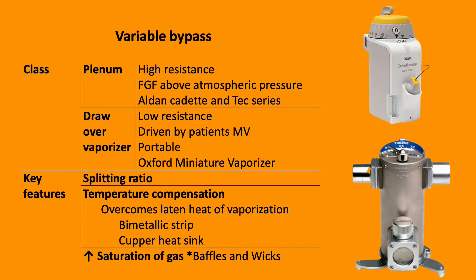Draw-over vaporizers are low resistance, driven by the patient's minute ventilation — they are portable. An example is the Oxford Miniature Vaporizer, shown in the bottom right corner. The key features of a plenum vaporizer are: splitting ratio, temperature compensation with the bimetallic strip and copper heatsink, and the importance of saturation of the gas via baffles and wicks.